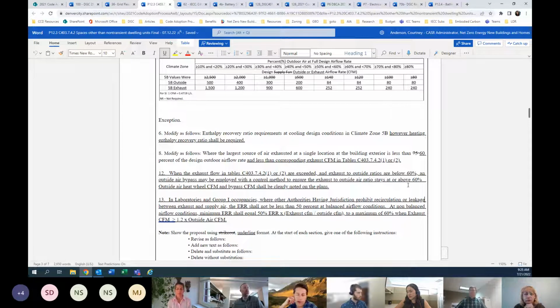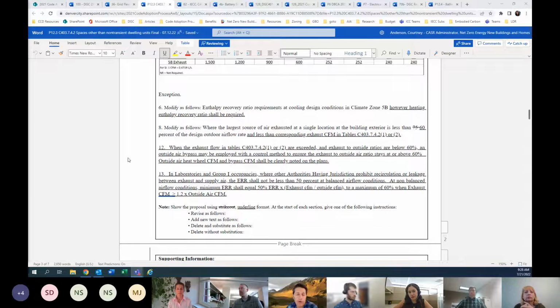Number 12 is just a designer's point to give them an alternate on how to design energy recovery, to let people know if their ratio is below 60% but above the table threshold, that they can do a bypass on the outside air. And then lastly, the lab exception allows for a lower enthalpy recovery ratio, which was apparently the reason 50% was chosen in the first place, was for labs instead of the other way around. So hopefully I didn't go too fast and lose everybody. I know that was a lot, so I'm sure there's some questions.